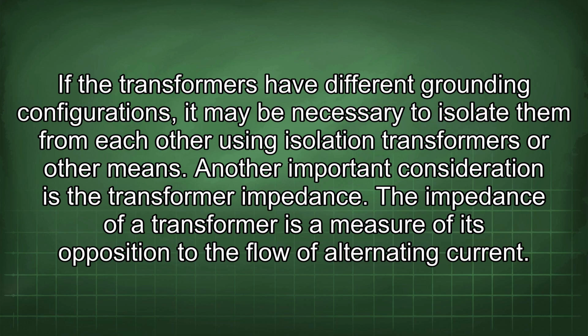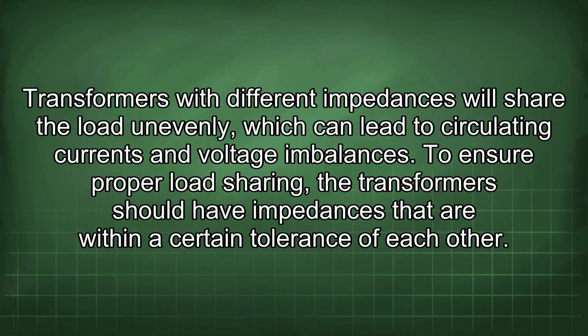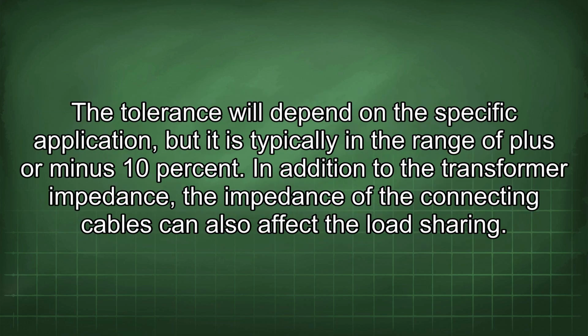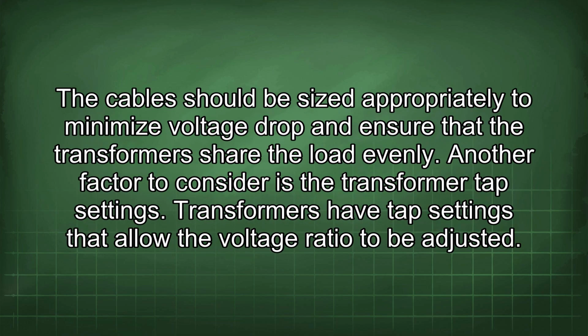The impedance of a transformer is a measure of its opposition to the flow of alternating current. Transformers with different impedances will share the load unevenly, which can lead to circulating currents and voltage imbalances. To ensure proper load sharing, the transformers should have impedances that are within a certain tolerance of each other. The tolerance will depend on the specific application, but it is typically in the range of plus or minus 10%. In addition to the transformer impedance, the impedance of the connecting cables can also affect the load sharing. The cable should be sized appropriately to minimize voltage drop and ensure that the transformers share the load evenly.